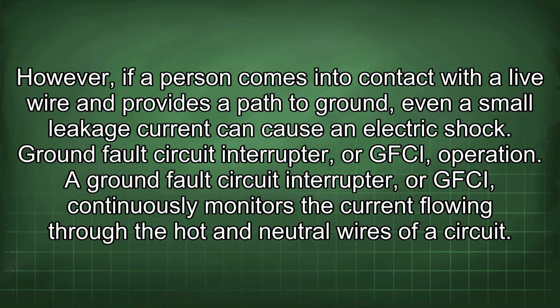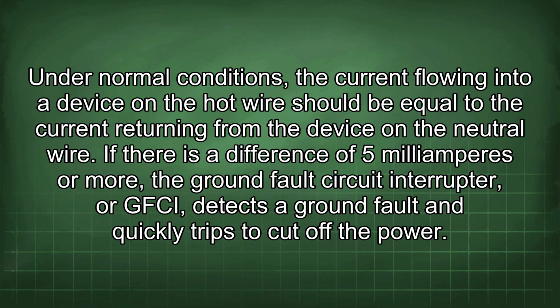GFCI operation. A GFCI continuously monitors the current flowing through the hot and neutral wires of a circuit. Under normal conditions, the current flowing into a device on the hot wire should be equal to the current returning from the device on the neutral wire. If there is a difference of 5 mA or more, the GFCI detects a ground fault and quickly trips to cut off the power.